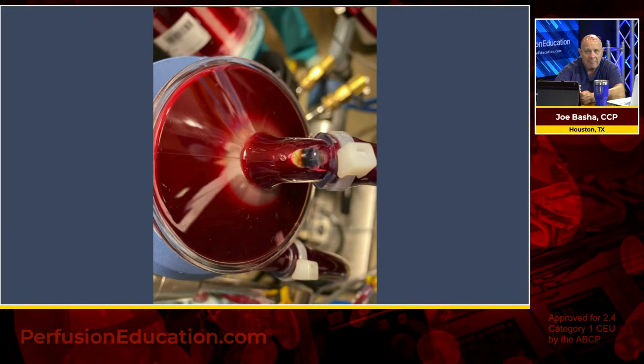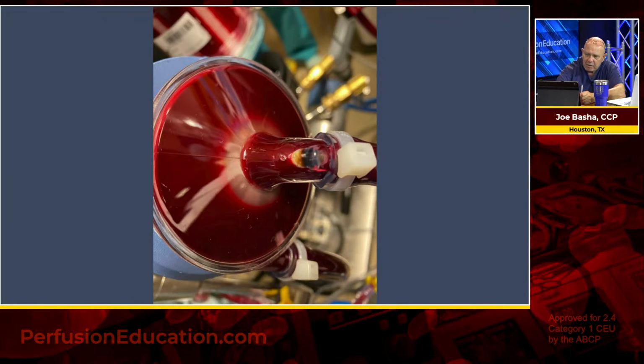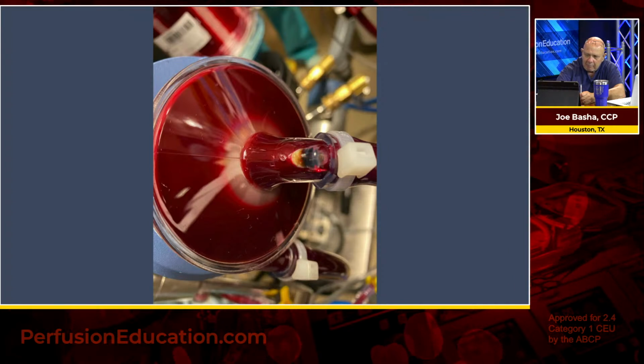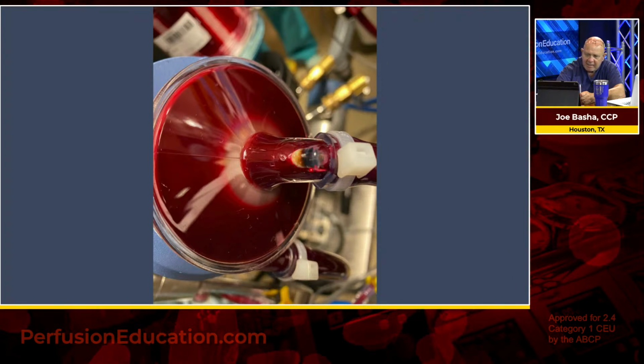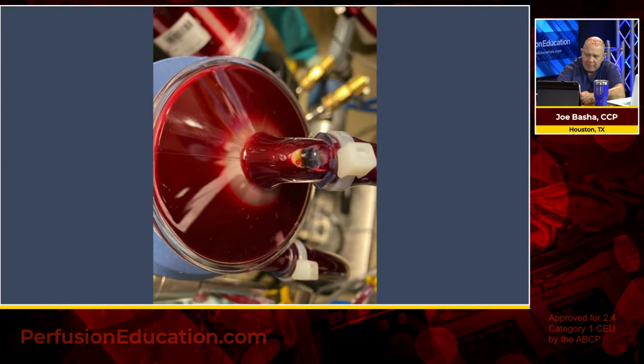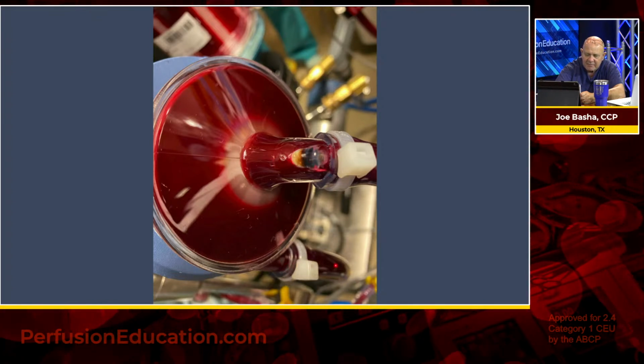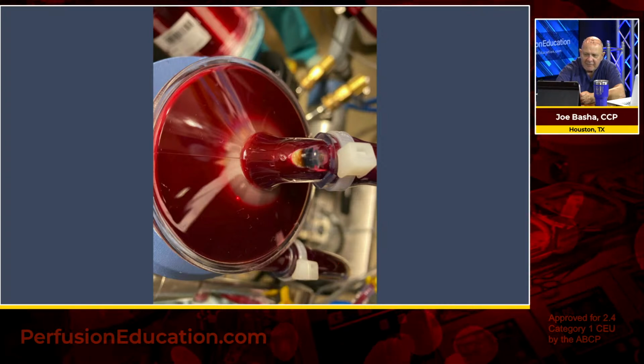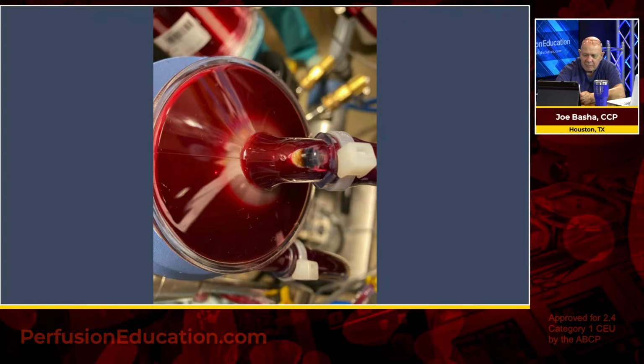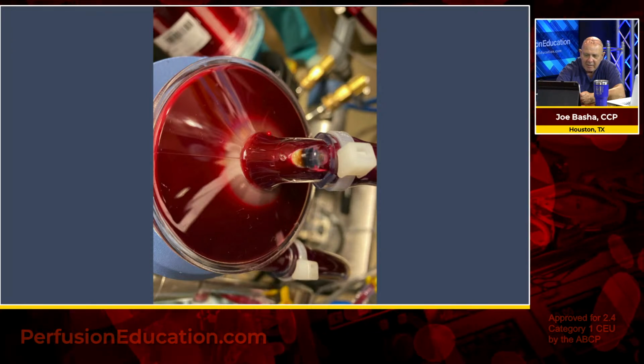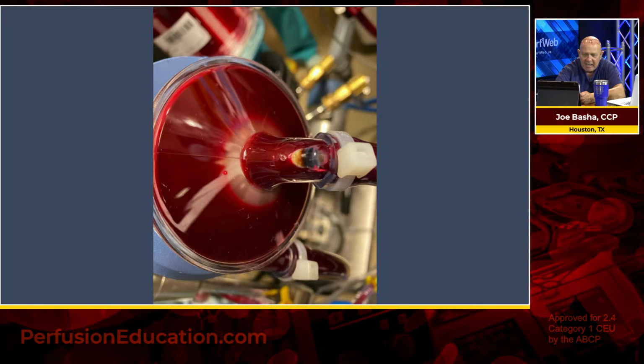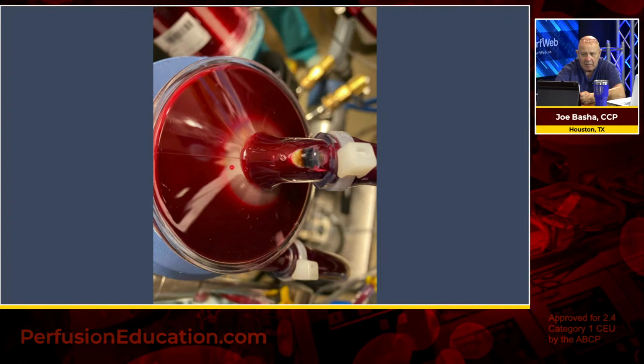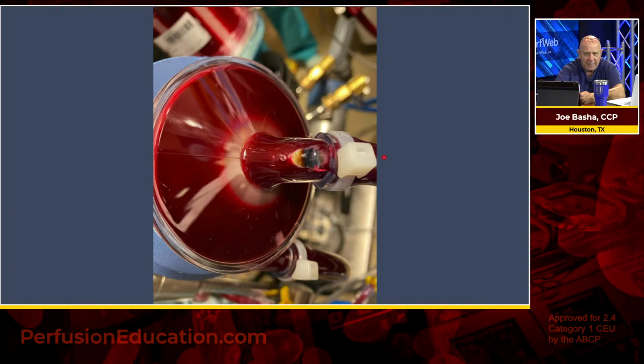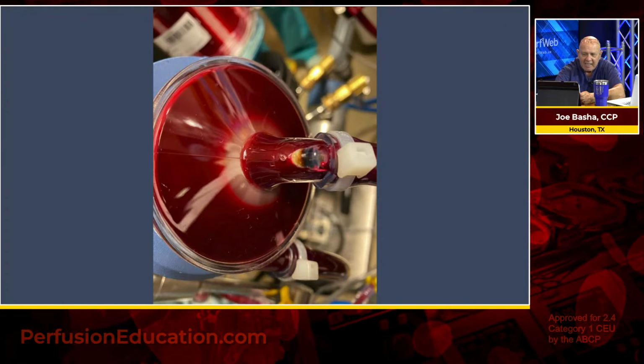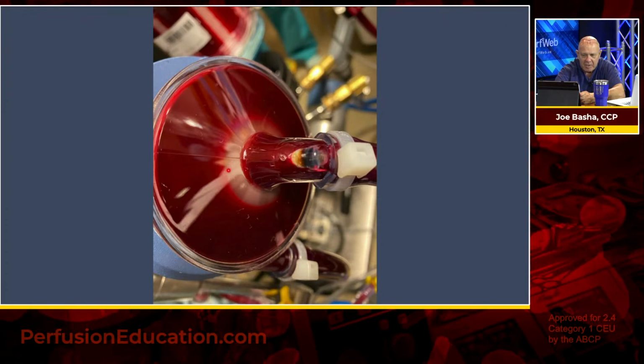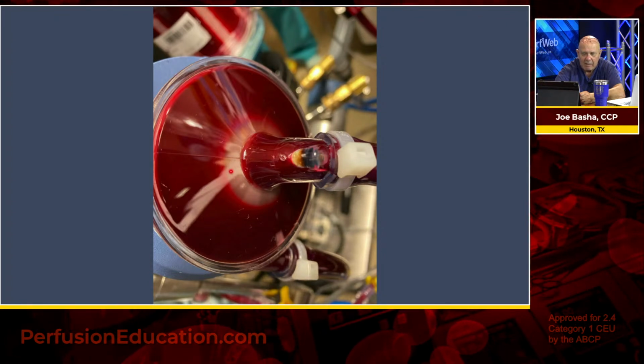This is one of my cases, and if you look right here, you see a big clot right there at the inlet of the pump. This is the inlet of the pump, or the negative side. This is the positive side of the pump, or the outlet. And if you look, you see this ring of white right here, and this is actually cavitation. That's air, but that air didn't come from the patient, didn't come from a source outside. It came from the negative pressure and basically drawing gas out of solution.